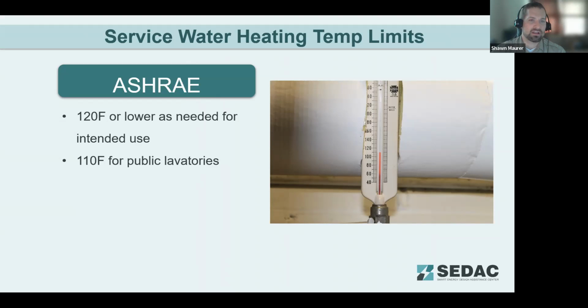For service water heating temperature limits, ASHRAE does specify some fairly strict limits that not only save energy, but reduce the potential for scalding injuries from use of overheated water. Facilities with at-risk populations may need to run higher temperatures in their tanks to prevent Legionnaires' disease, and then have mixing valves or something on the distribution system to meet these set point requirements. For ASHRAE, they do specify that 120 Fahrenheit or lower as needed for the intended use, and then 110 Fahrenheit for public lavatories, hand washing stations, essentially.